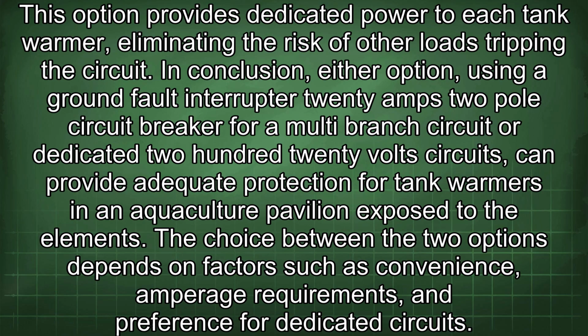In conclusion, either option, using a ground fault interrupter 20 amps 2-pole circuit breaker for a multi-branch circuit or a dedicated 220 volt circuit, can provide adequate protection for tank warmers in an aquaculture pavilion exposed to the elements. The choice between the two options depends on factors such as convenience, amperage requirements, and preference for dedicated circuits.